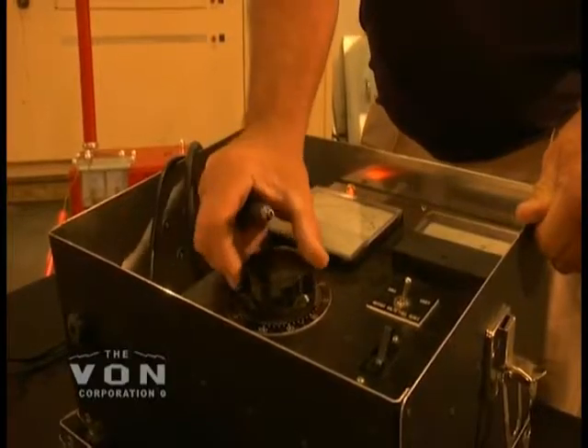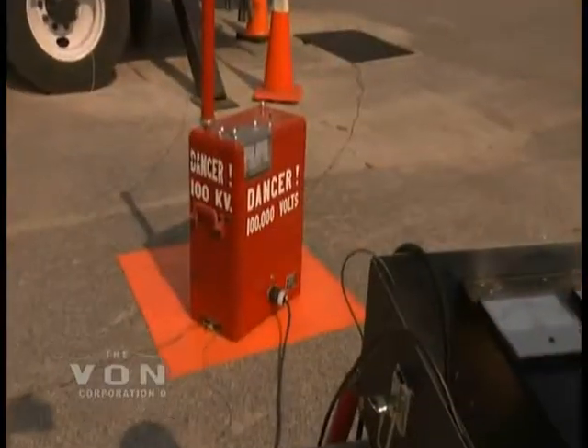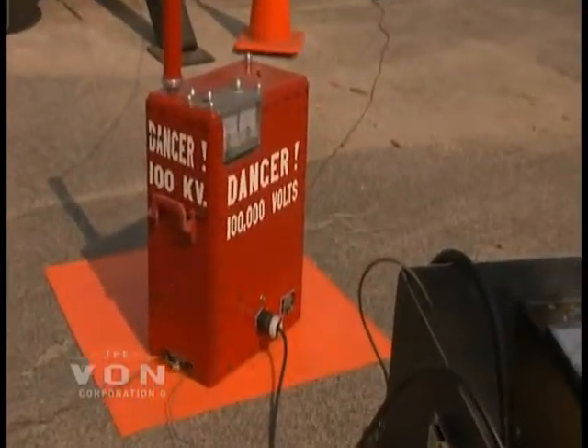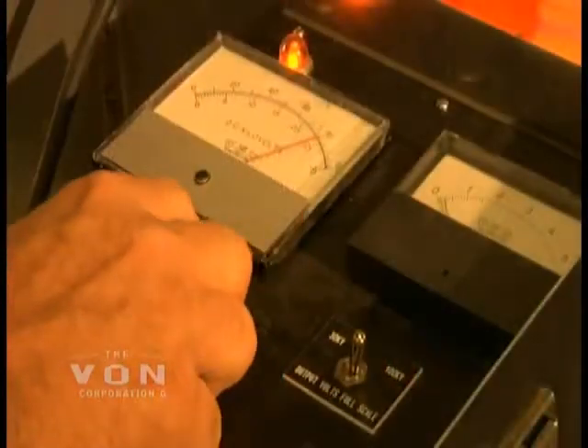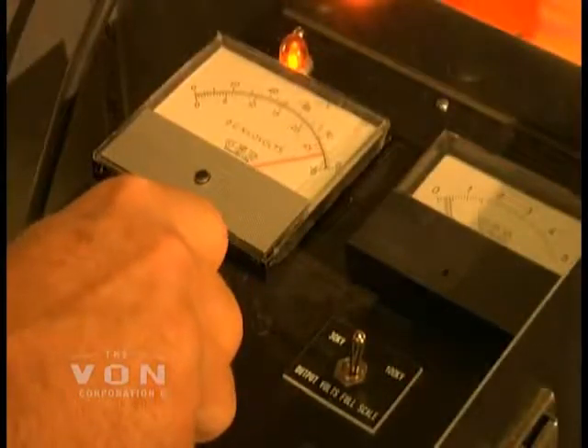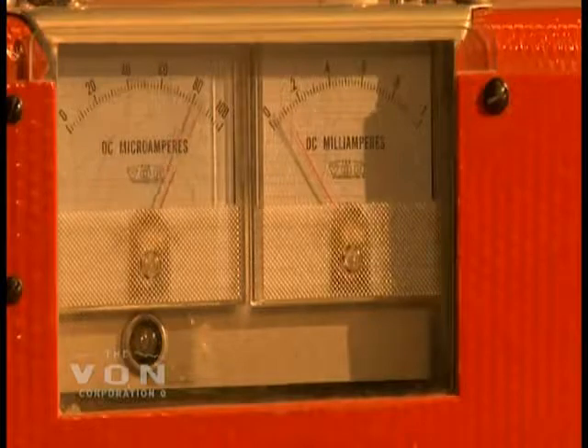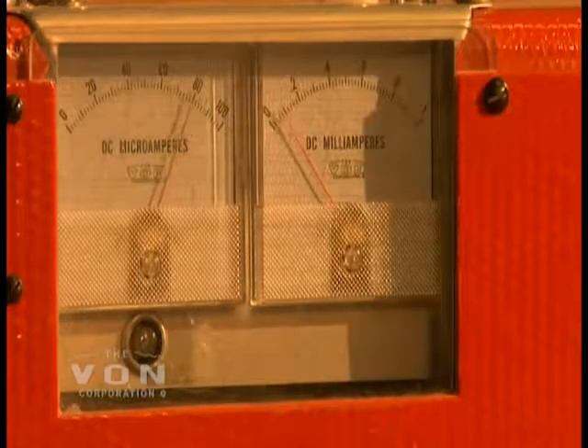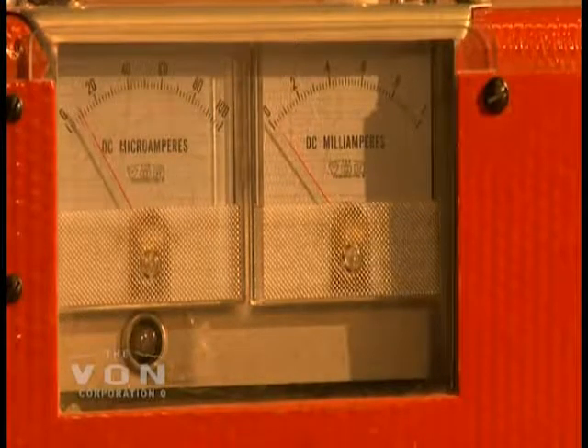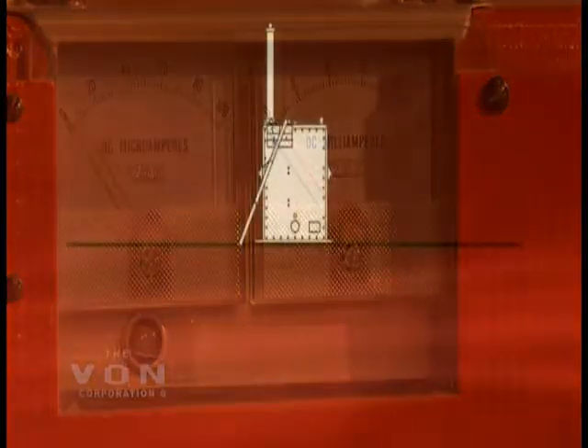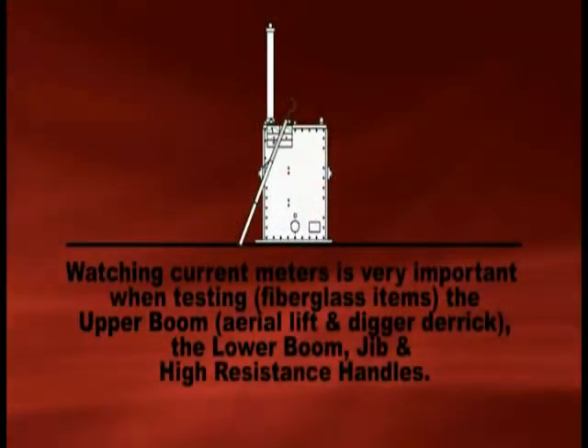When applying your test voltage, you need to stay in constant reminder that you are watching your microamps and milliamp gauges on the red test box. Don't just run your high voltage control knob up to voltage. Keep a constant watch on your microamps and milliamps to ensure that you do not exceed your allowable microamps and milliamps when running up to test voltage.